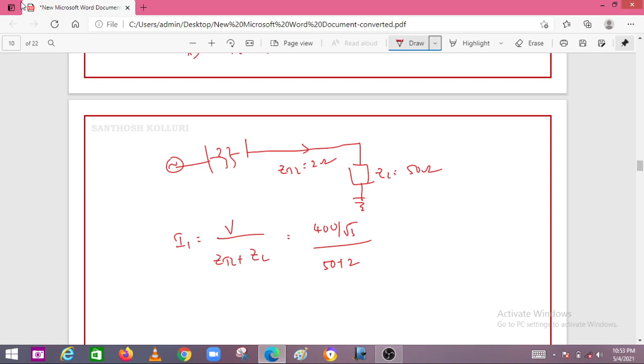Similarly, fault impedance means what here? Like this is a generator, transformer, and this is a load. For example, load is 50 ohms and the transmission line is 2 ohms, let me say. So during normal operation, the current flowing through the transmission line is operating voltage divided by transmission line plus load. Let us take 400 by root 3 as the normal voltage. Z transmission line is 2 ohms and ZL is 50 ohms. So this will be 50 plus 2, which is equal to 52. So here my current will be approximately 8 by root 3 kilo ampere, right?